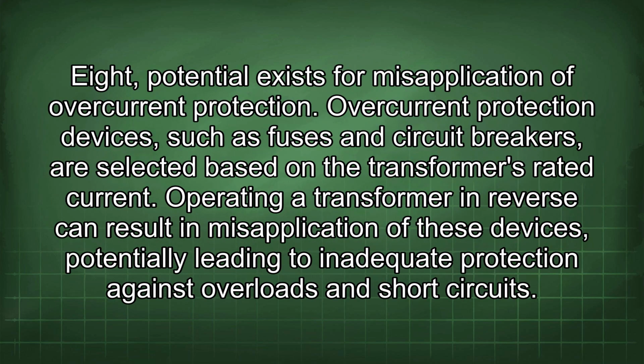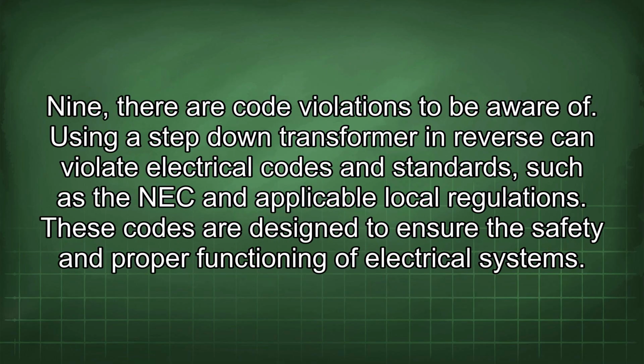8. Potential exists for misapplication of overcurrent protection. Overcurrent protection devices, such as fuses and circuit breakers, are selected based on the transformer's rated current. Operating a transformer in reverse can result in misapplication of these devices, potentially leading to inadequate protection against overloads and short circuits.